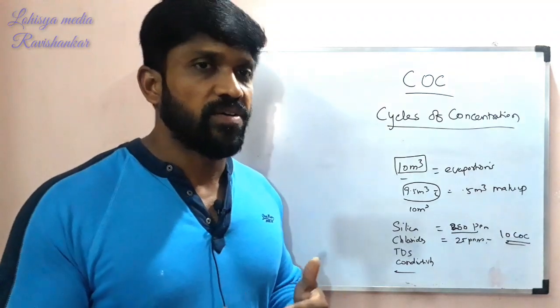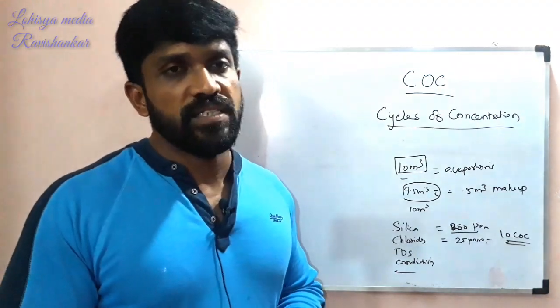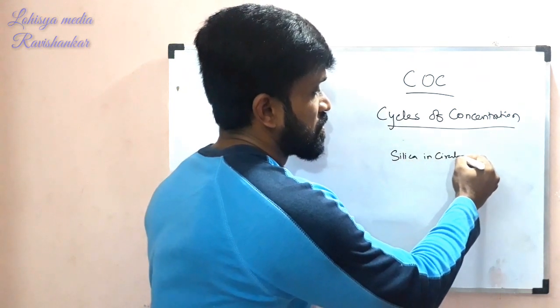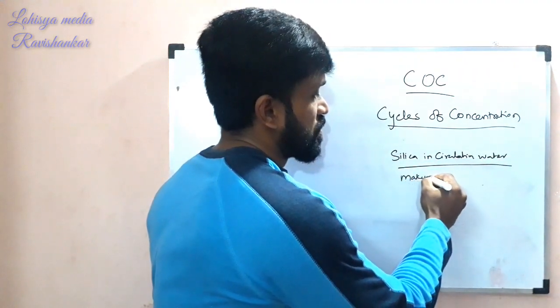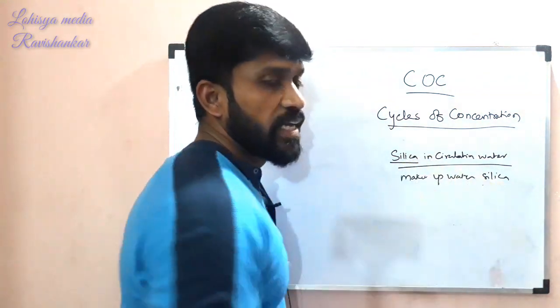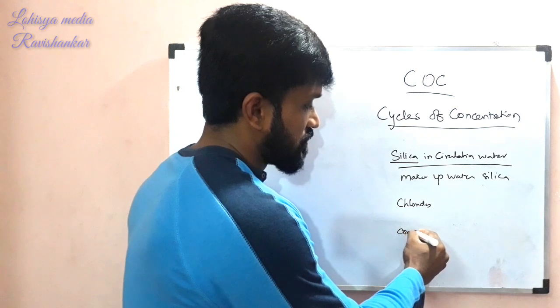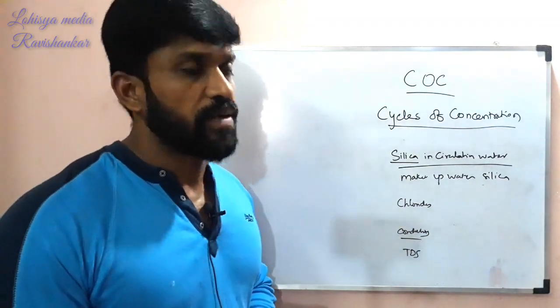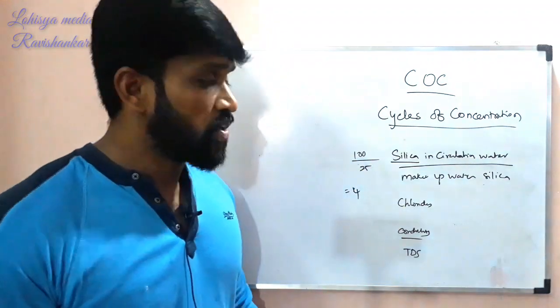Higher COC means better water conservation and energy efficiency — less makeup water is consumed. The COC formula is: COC equals the parameter value in circulation water divided by the parameter value in makeup water. For example, silica at 25 ppm makeup versus 100 ppm circulation gives 4 COC.